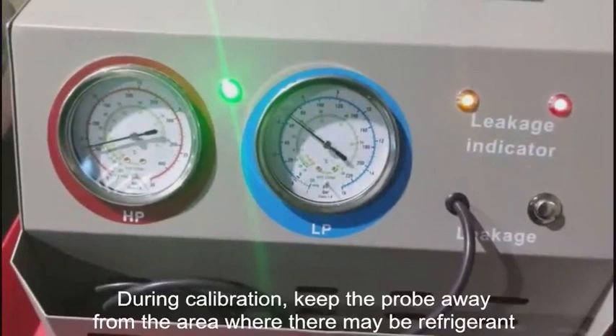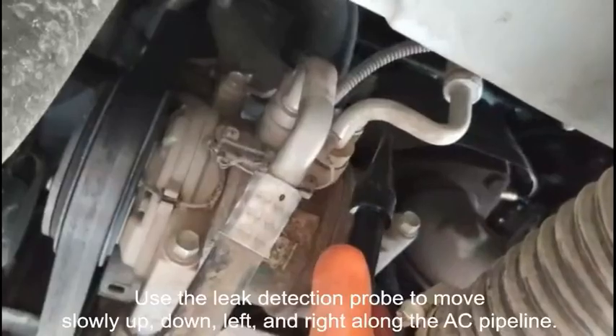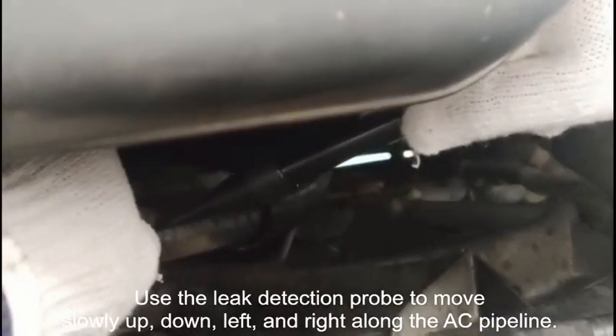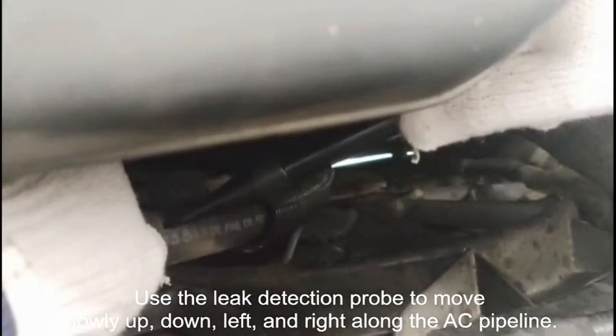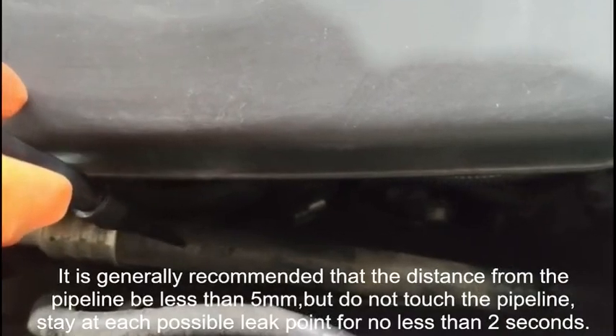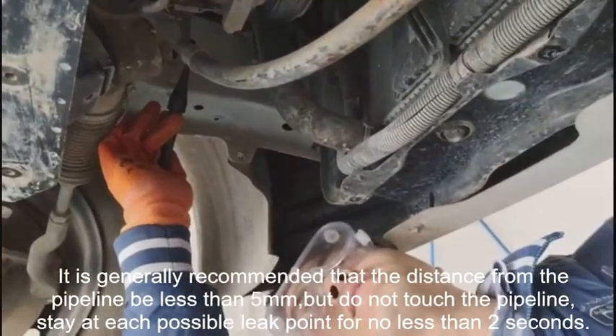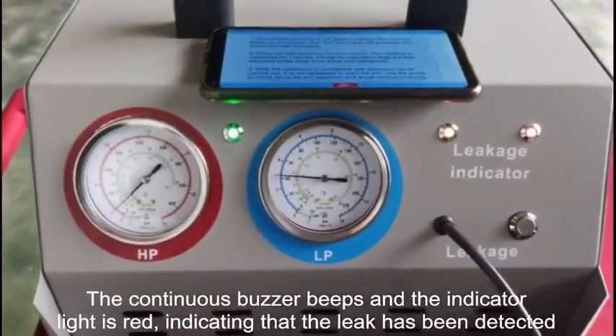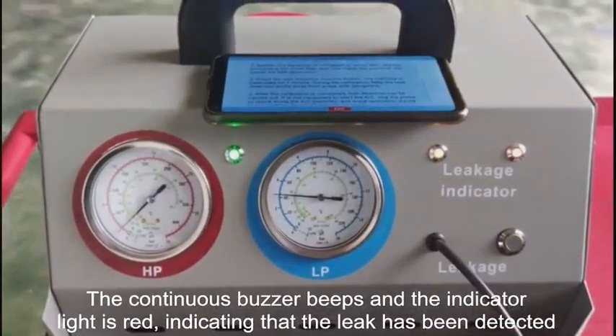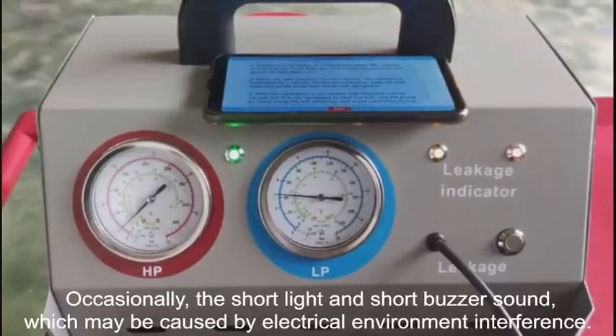During calibration, keep the probe away from the area where there may be refrigerant. Use the leak detection probe to move slowly up, down, left, and right along the AC pipeline. It is generally recommended that the distance from the pipeline be less than 5 mm, but do not touch the pipeline. Stay at each possible leak point for no less than 2 seconds. The continuous buzzer beeps and the indicator light is red, indicating that the leak has been detected. Occasionally, a short light and short buzzer sound may be caused by electrical environment interference.